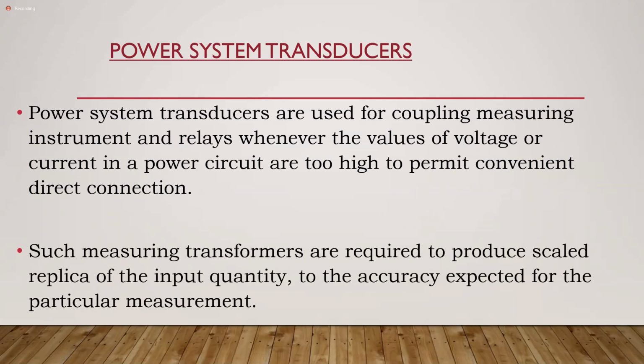So we say that these transducers, or measuring transformers, however we want to call them, must produce that scaled replica of the input. If you take it from the standpoint of measuring instruments for revenue purposes, in large facilities the currents will be way in excess of 200 amperes. If the transducers being used are not accurate, then either the utility or the customer will be robbed.